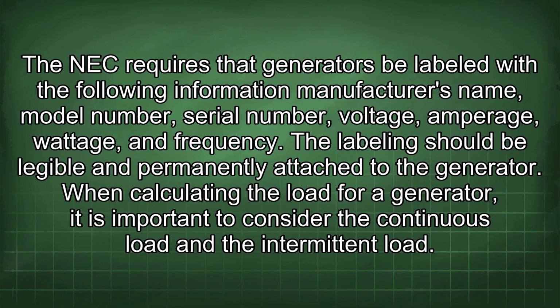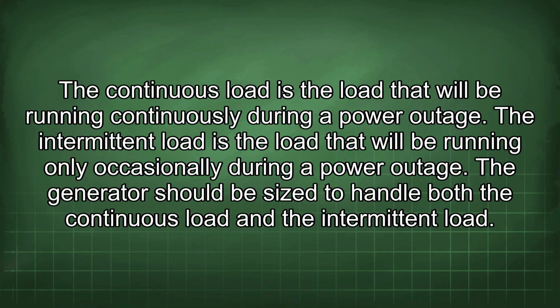When calculating the load for a generator, it is important to consider the continuous load and the intermittent load. The continuous load is the load that will be running continuously during a power outage. The intermittent load is the load that will be running only occasionally during a power outage. The generator should be sized to handle both the continuous load and the intermittent load.